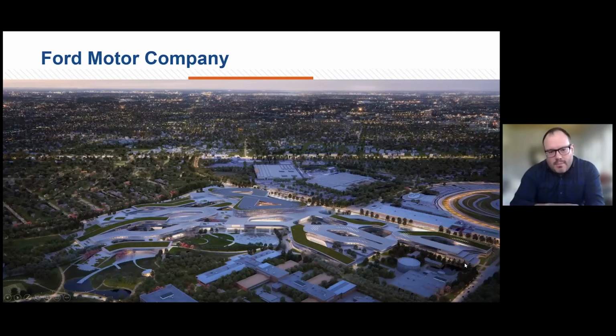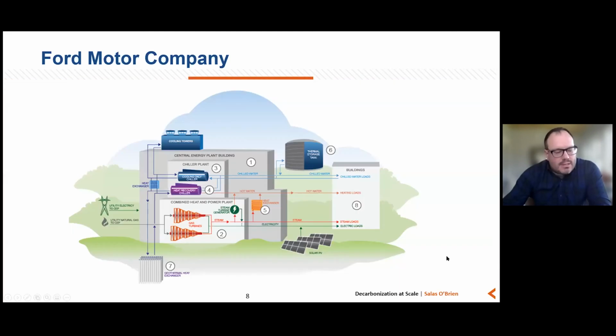This image is the master plan concept for the demolition of 4 million square feet on this campus and the addition of 6 million square feet to put the overall campus at about 9 million square feet of occupied space, which is a collection of research settings, engine test cells, as well as a lot of office and pretty typical commercial space from an officing perspective. The central energy plant is in the lower right corner of this. You can see there's a very large thermal storage tank, as well as the smaller tank, which is a fire protection tank. And the concept for the central energy plant there is far more like a hybrid system.